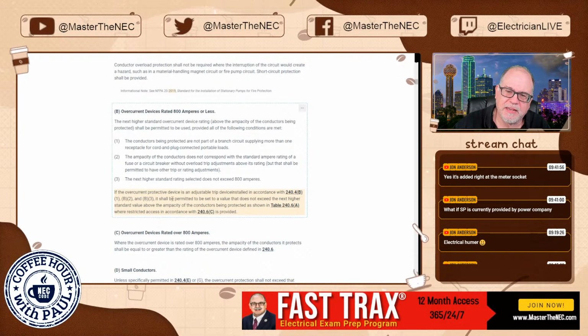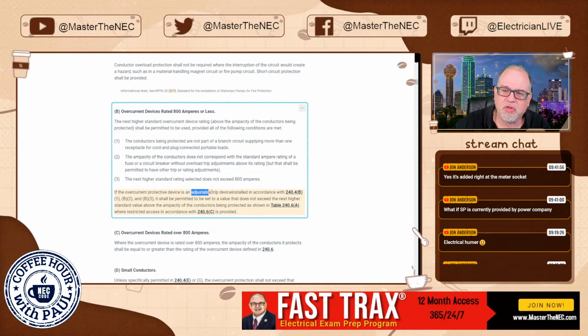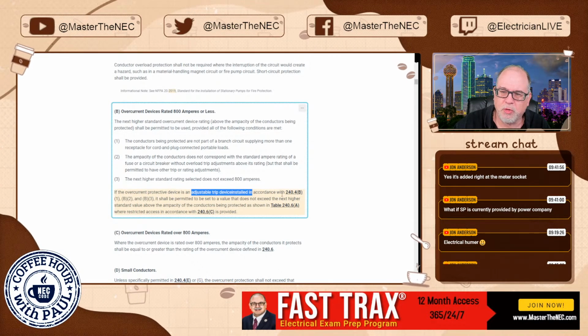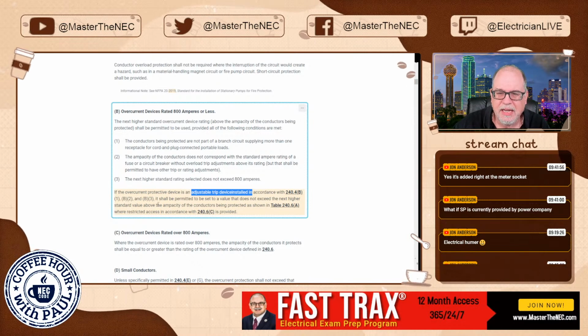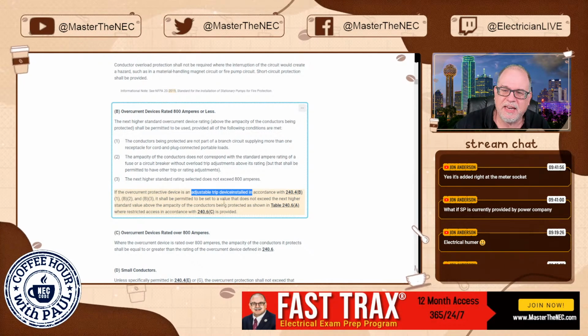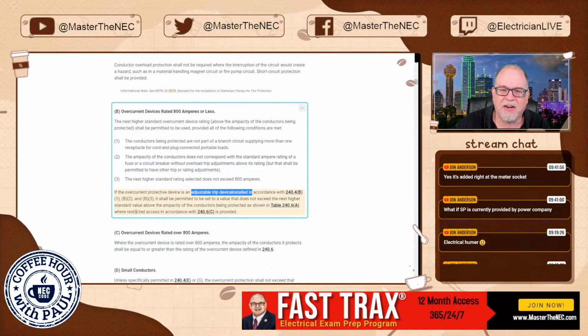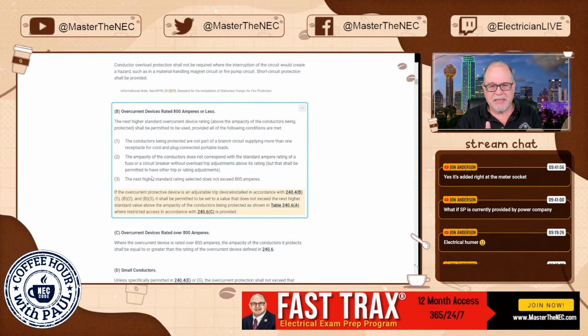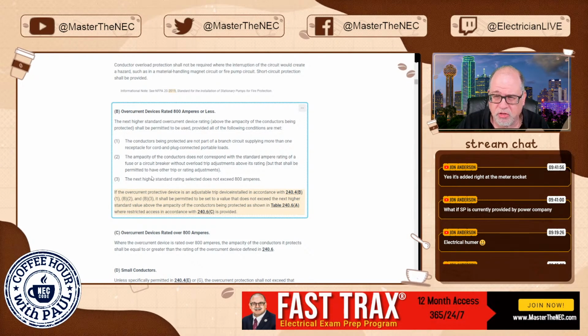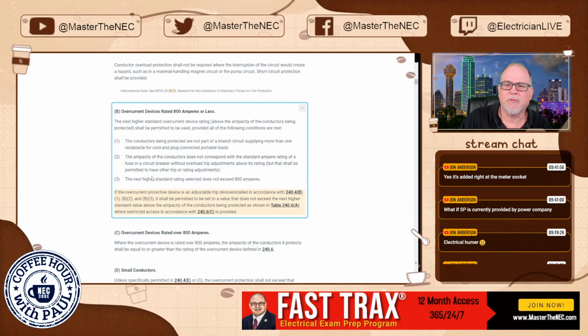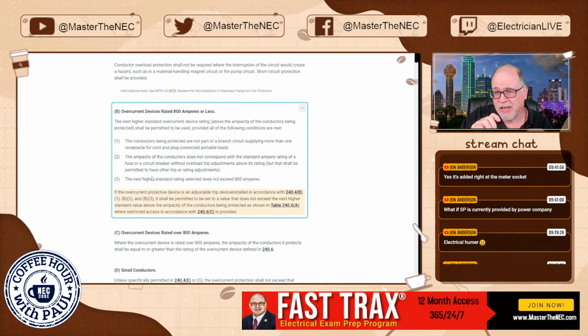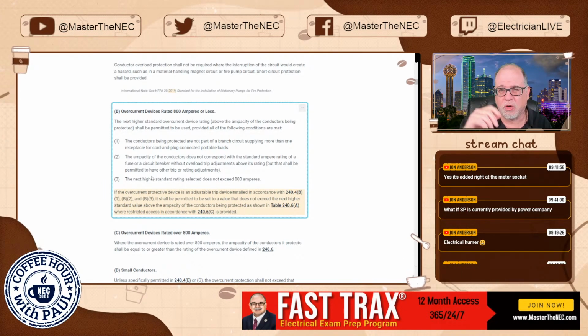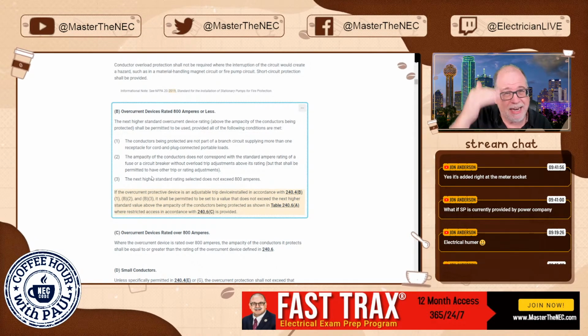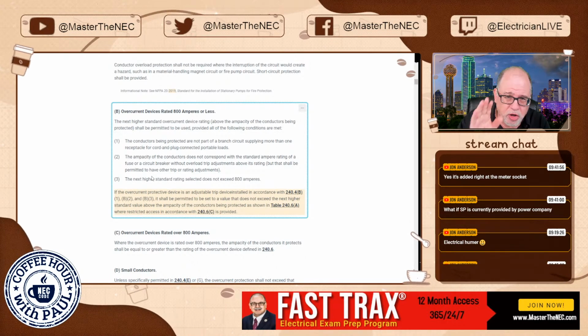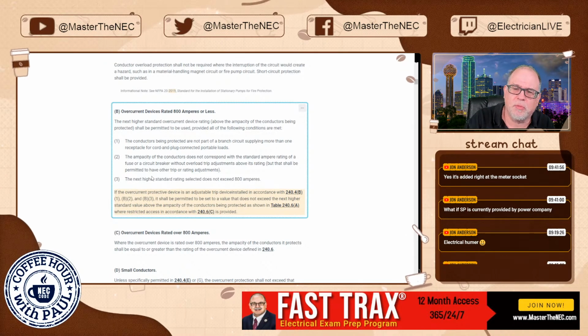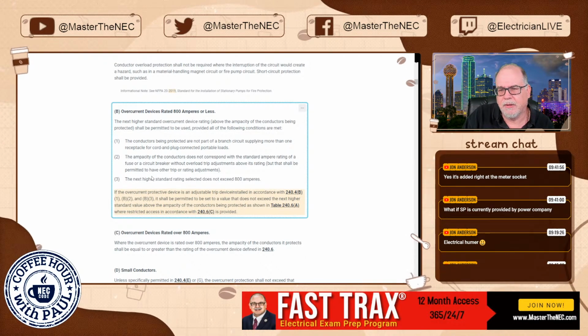It says if the overcurrent protected device is an adjustable trip device installed in accordance with 240.4(B)(1), (2), or (3), it shall be permitted to be set at the value that does not exceed the next higher standard value. Okay, so what this means, if you look at the 2020 edition, it didn't have an allowance in there for an adjustable trip device. In other words, you can turn it up to the next standard size. Now, of course, usually it is a large range that you can adjust these to. But in order to use this rule, we're now going to let you use an adjustable trip circuit breaker, okay?